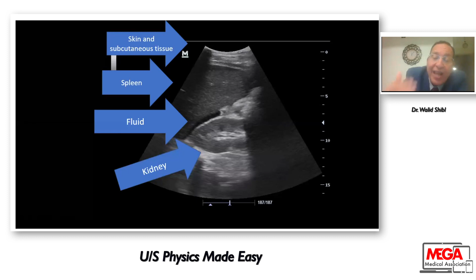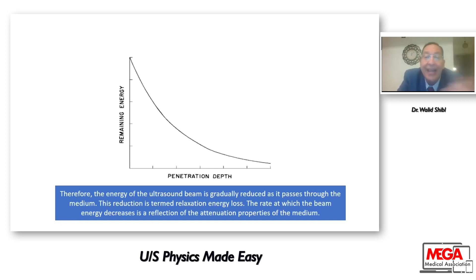Unfortunately, the energy of the ultrasound beam is gradually reduced as it passes through the medium. This reduction is termed attenuation, or energy loss. The rate at which the beam energy decreases is a reflection of the attenuation properties of the media. This is another concept. You need to know the tissue is determining everything. And there is what's called the attenuation coefficient, the ability of the tissue to attenuate and absorb the ultrasound. As you see here, in skull bones it is 20 decibel per centimeter. For every centimeter through the skull bone, the ultrasound beam will lose 20 decibel, too much.